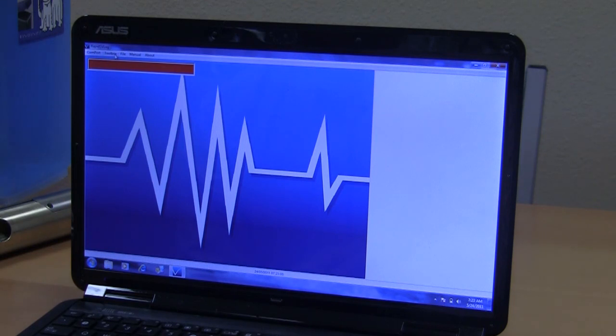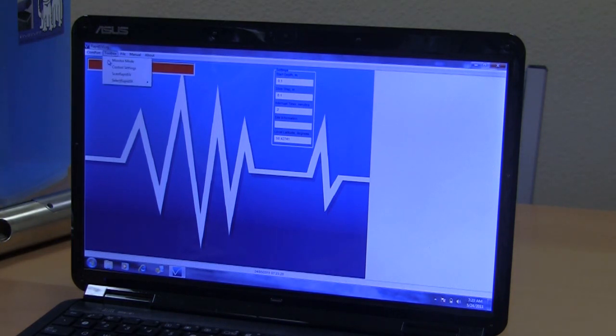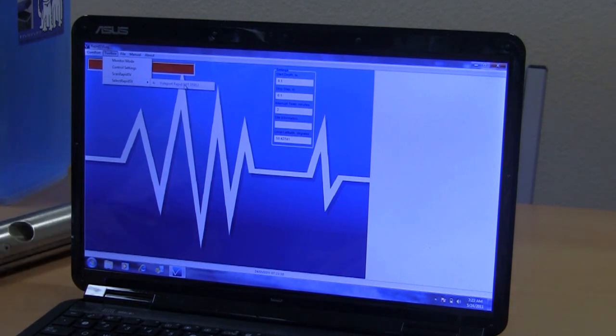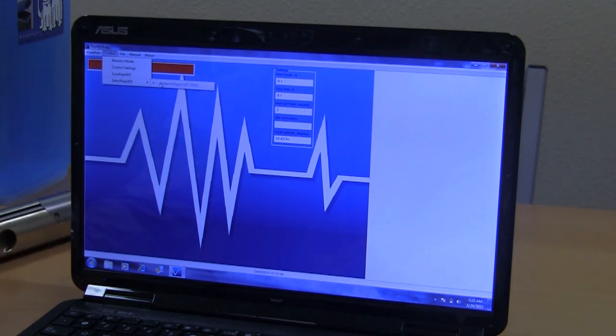So, check control settings, 0.1 meters. The probe's going to start logging when it reaches 0.1 meter depth. It's going to stop logging when it is raised upwards 0.1 meters, and the probe's going to be interrupted every 2 minutes. So what we can do is set the probe running by clicking on monitor mode. Firstly, we just confirm here, select RapidSV, this is selected, the same serial number is on the probe, SVT 35912, so nothing will change unless we select on the RapidSV probe. This will stay linked to this probe here.